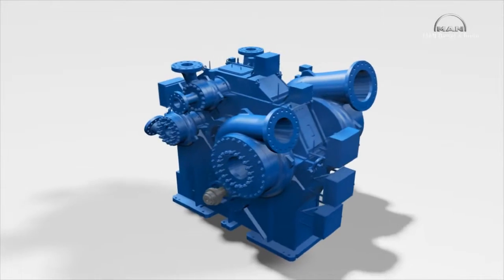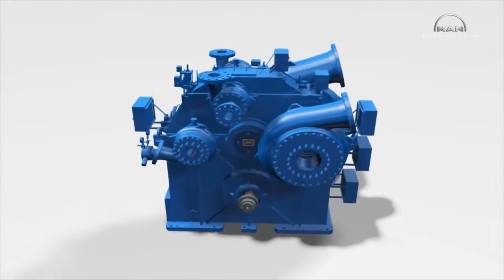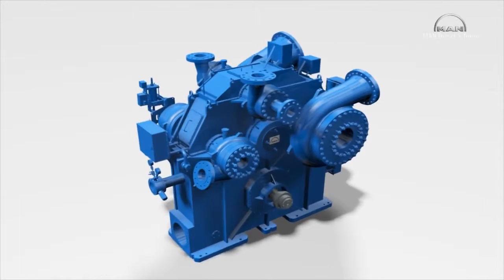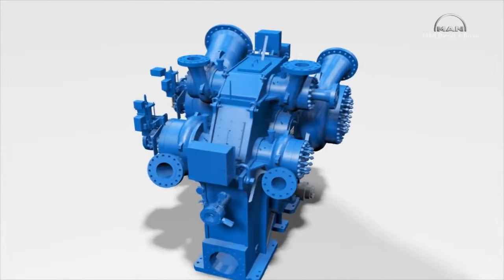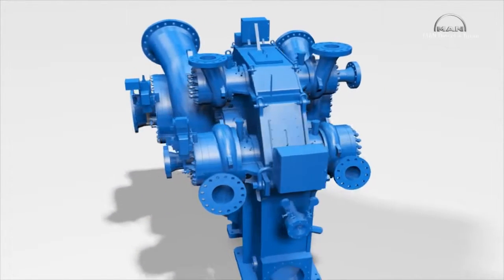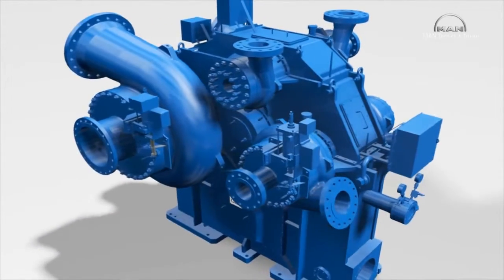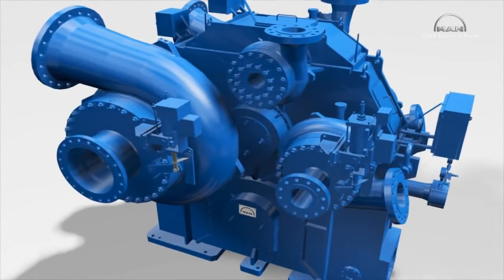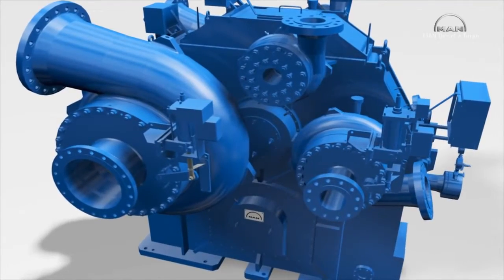This compressor has six stages, arranged in two sections. Downstream of the second stage, the customer can draw off a specific volume at medium pressure. The remainder is further compressed to the desired discharge pressure by the second section consisting of stages three to six.